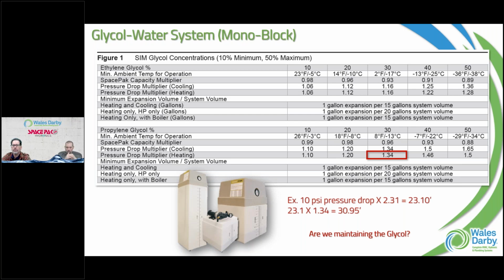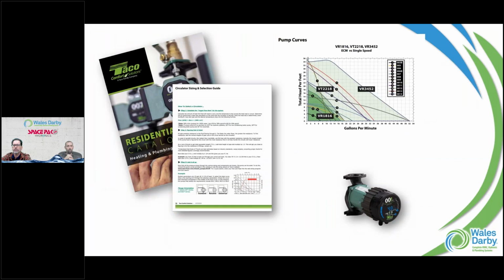Right? Anything to say to that? No, good, beautiful. So obviously, two bits of information we're going to need are the GPM we have to move and the total resistance we have to overcome for that circulator. Once we get that information, we can come in here. This is the Taco full line catalog you got in your handout section, so don't forget to download that. We'll come into this back section and look at some of these pump curves and figure out which circulator makes sense.